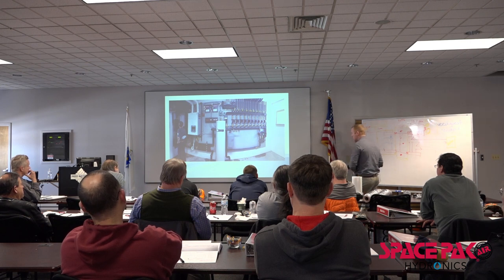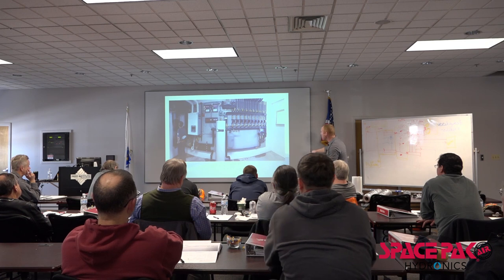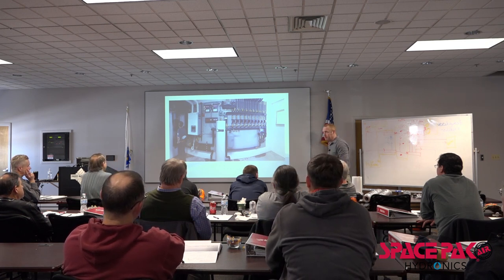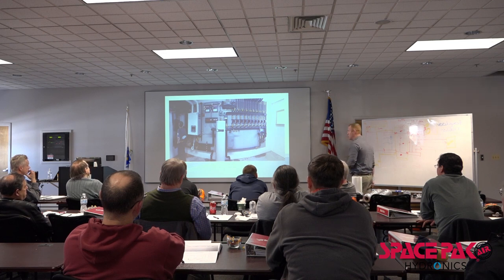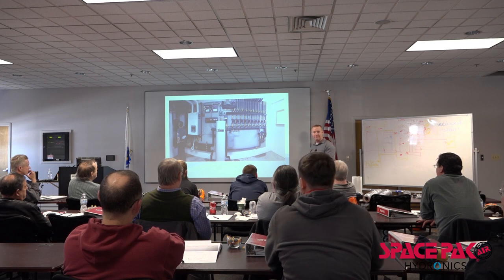Another project here, chilled water system, lots and lots of insulation. What do you see down here? Yep. Drip, drip, drip, drip, right? So it looks real cool. If you ever do a really nice chilled water, you'll take pictures before you put the insulation on.